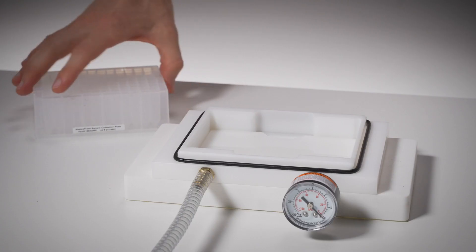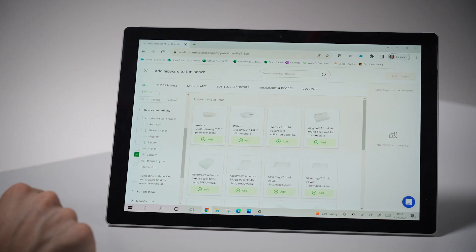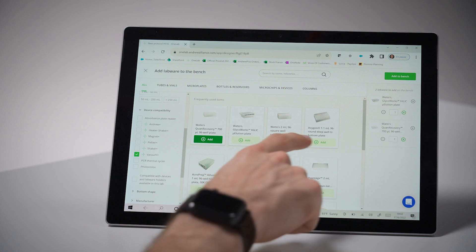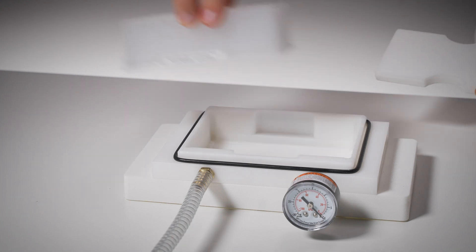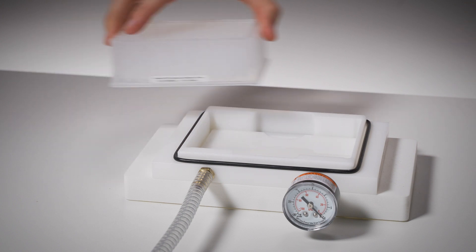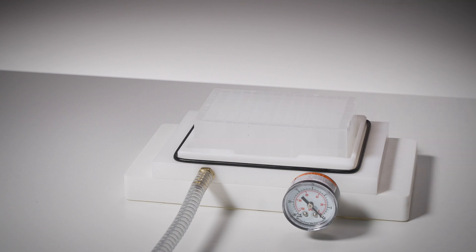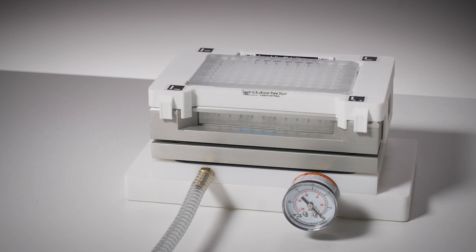The structure of this device allows for the placement of a collection labware within its inner chamber, and easy placement of an extraction labware on top. Vacuum Plus is only compatible with 96-well plate formats, but there are many to choose from. This naturally includes a list of both extraction plates and collection plates, so you can mix and match the configuration that best suits your volume and sorbent requirements. Some tweaking may be necessary for properly positioning your collection labware within Vacuum Plus. To this end, we recommend acquiring dedicated shims that allow you to physically prop up or lower your collection plates in function of your elution plate formats. This is indispensable to avoid cross-contaminations while also ensuring that your samples are properly collected.